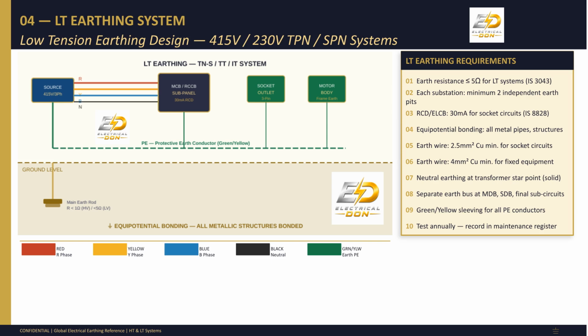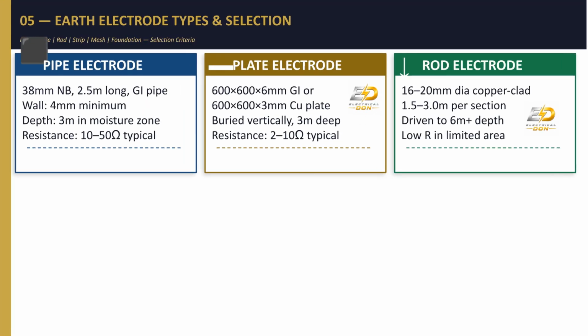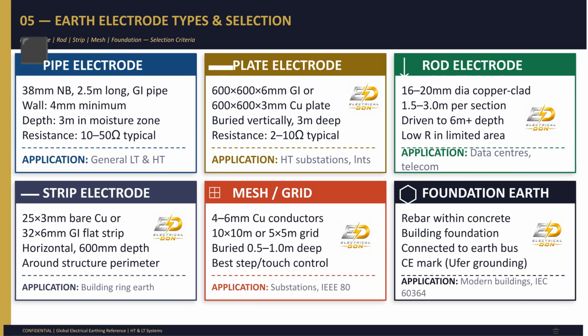Requirements include a minimum of 2 independent earth pits per substation and mandatory use of 30 milliamperes residual current devices for socket circuits. Equipotential bonding is crucial, connecting all metal pipes and structures. PE conductors must be green and yellow sleeved. Electrode selection criteria are based on soil resistivity and application. Options include pipe, plate, rod, strip, mesh/grid, and foundation earth, each with specific dimensions and typical resistance ranges.